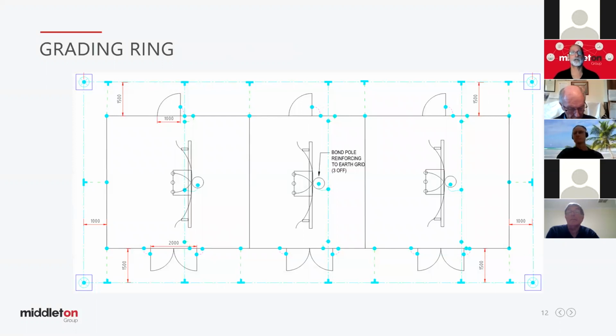Interestingly enough, down the bottom there, you'll see that the grading ring's out by 1.5 metres to cater for if a gate is open and someone's touching an open gate. We've managed to increase the soil voltage up there towards EPR to reduce the voltage differential someone may be exposed to. So this is a grading ring that helps in secondary mitigation. It actually adds to the whole grid as well in this situation, and will reduce the RG to reduce the EPR as well.